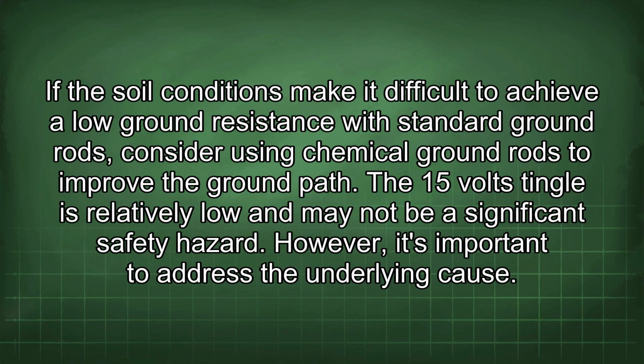If the soil conditions make it difficult to achieve a low ground resistance with standard ground rods, consider using chemical ground rods to improve the ground path. The 15 volts tingle is relatively low and may not be a significant safety hazard. However, it's important to address the underlying cause.